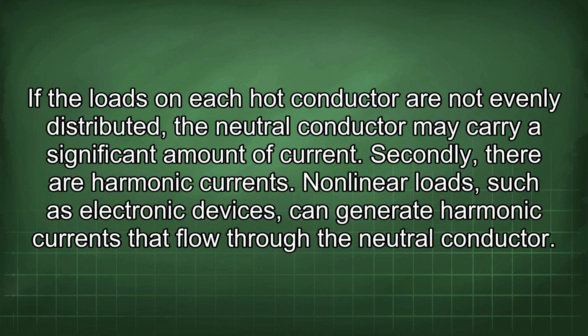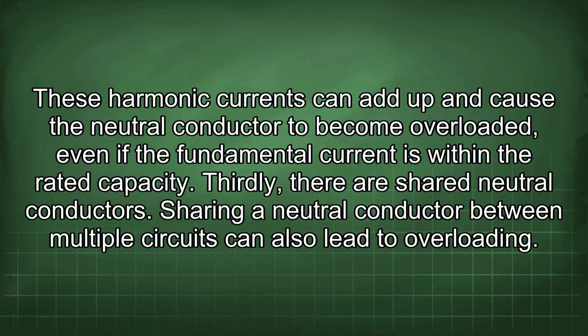Secondly, there are harmonic currents. Nonlinear loads, such as electronic devices, can generate harmonic currents that flow through the neutral conductor. These harmonic currents can add up and cause the neutral conductor to become overloaded, even if the fundamental current is within the rated capacity. Thirdly, there are shared neutral conductors.